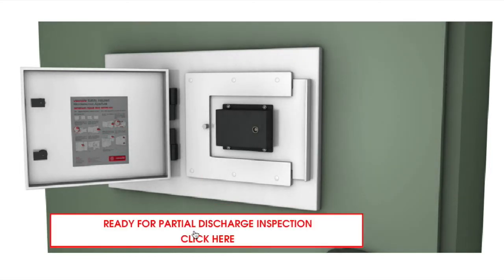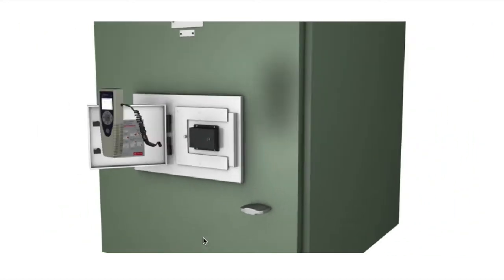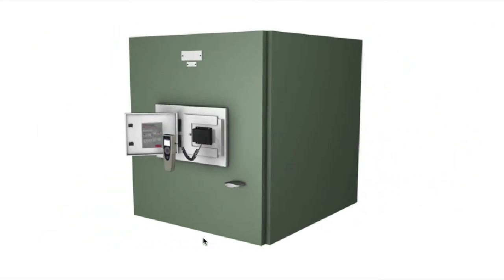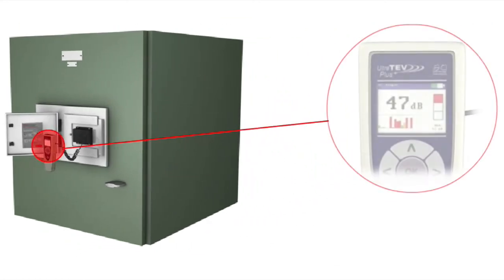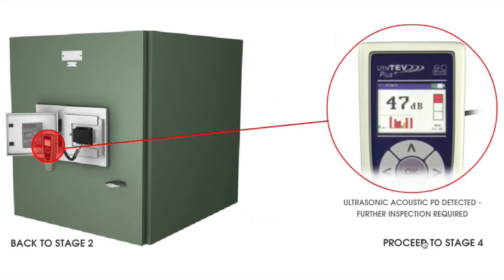Once in place, the UltraTeV Plus connects to the slide and displays the ultrasonic decibel level inside the panel, which indicates partial discharge activity.